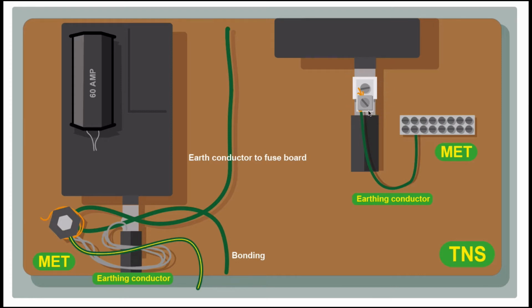If we've got this kind of setup, sometimes there's a clamp on the supply cable. You get various different types of clamps. The DNO might have done this, but often you see a DIY type job where somebody's used a BS951 bonding clamp on the supply cable. You shouldn't do that because the bonding clamp is designed to clamp around a copper pipe, and it does it by compression. It pulls tight onto it. You don't want to be pulling tight onto an electrical supply cable, because you could crush the cable and short out the connection. The cable's inside, and that's just going to cause mayhem. So don't be tempted to work on this at all. If it's loose, don't be tempted to try and nip it up.